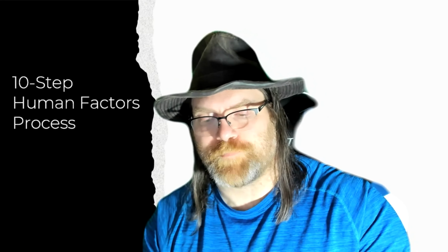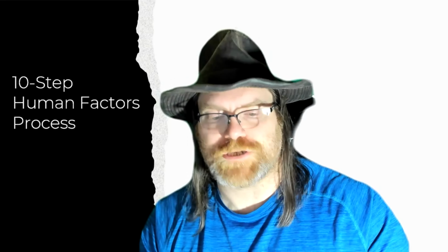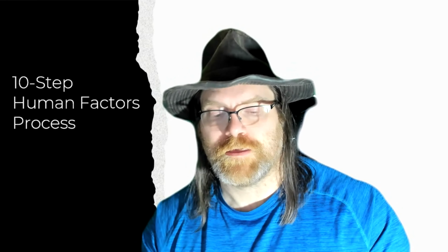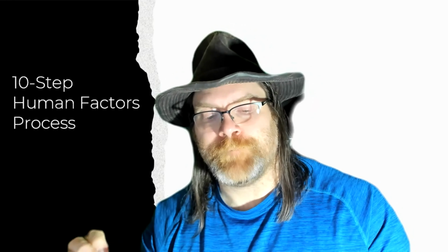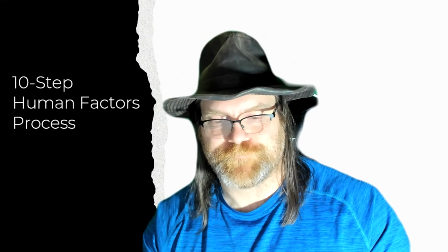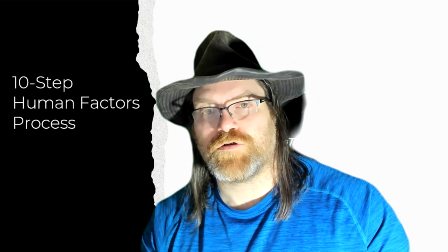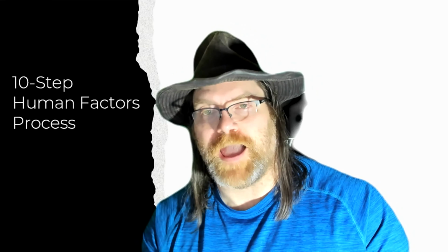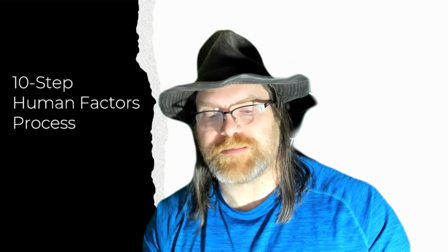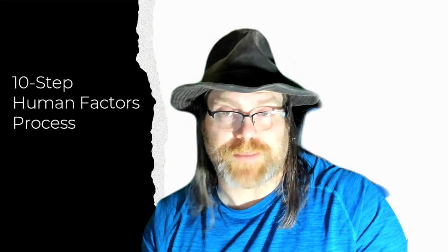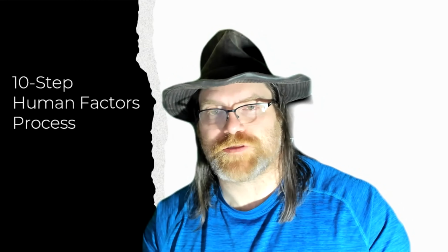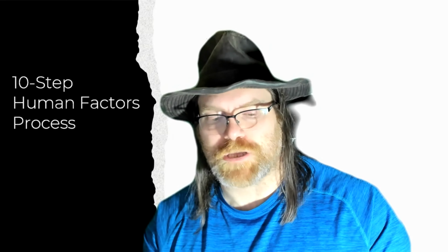Okay. The next step of the process, step 5, option analysis. So this is your risk control option analysis. You want to have in this section testable technical requirements relevant to the user interface. So every single one of these critical tasks, you need to identify, how am I going to test this? Either in formative testing or in summative testing. How am I going to test this? It could be benchtop testing even. Some sort of simulation to show how are you going to make sure that this risk control you implemented to prevent this use error actually works.